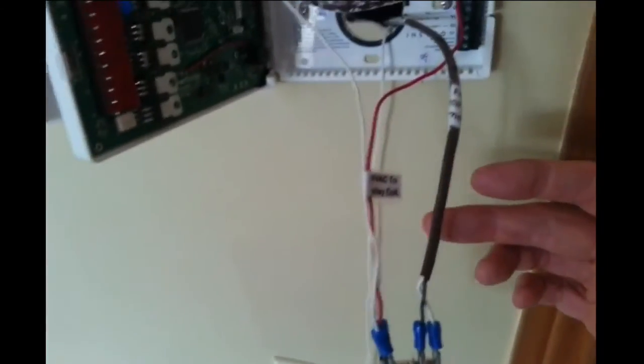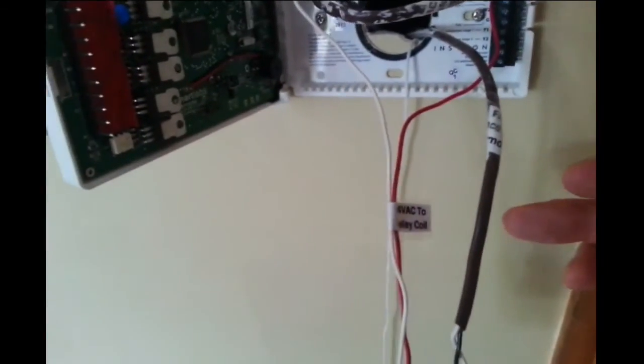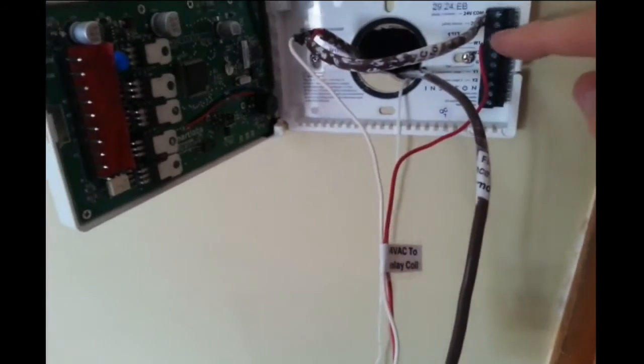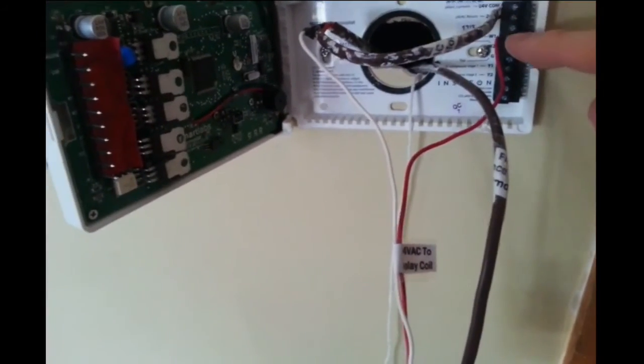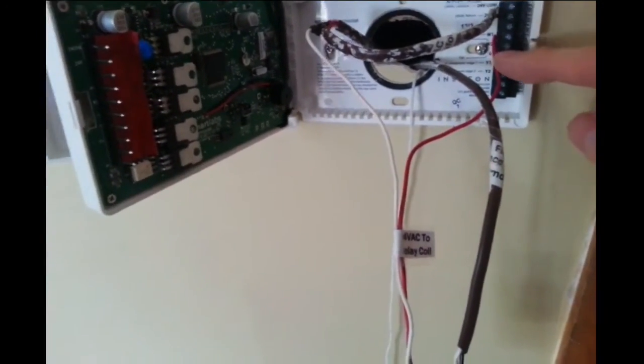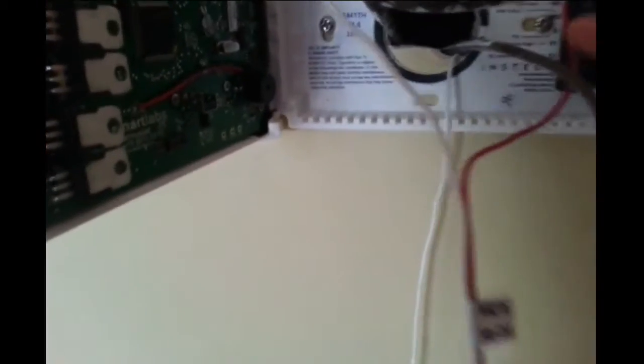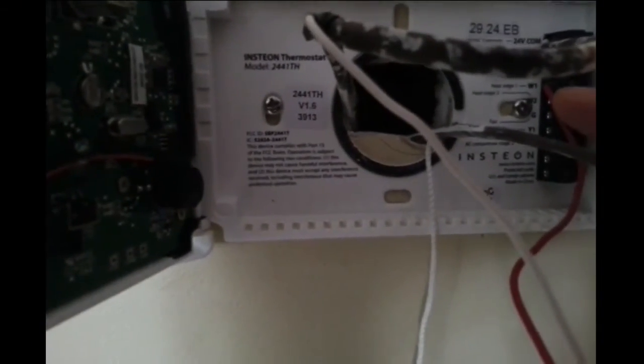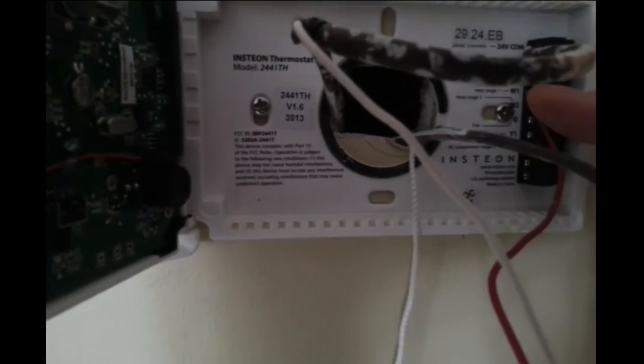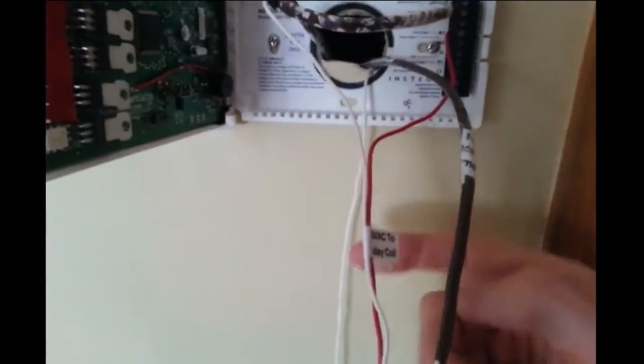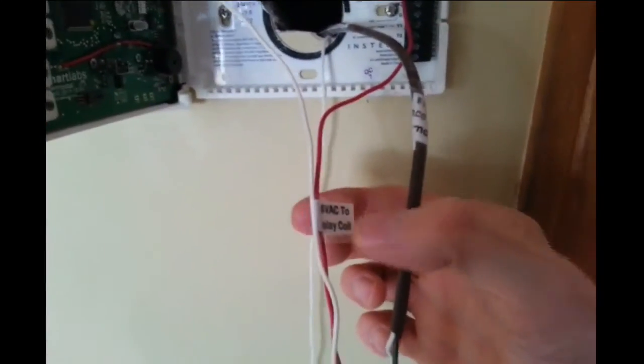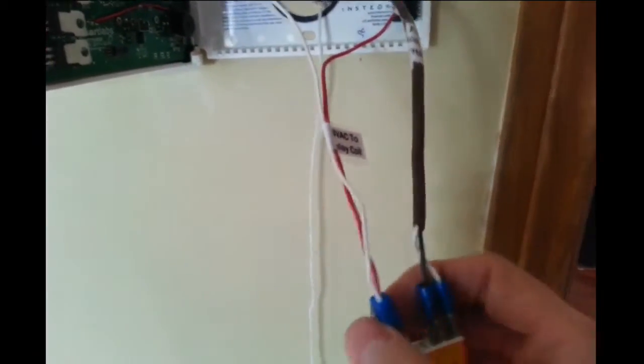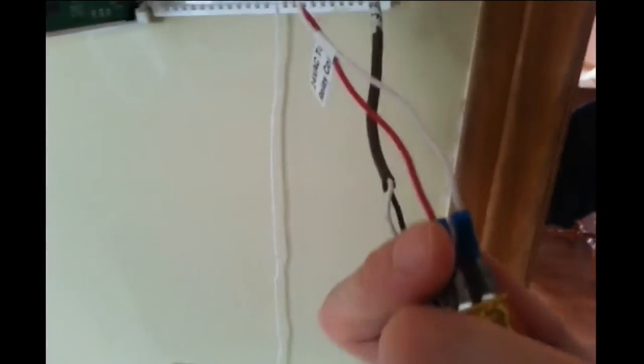So the other side of the 24-volt would come into the thermostat and then be fed out here whenever it needs heat. That's coming off of the W1 terminal on the thermostat, and then runs down to the other side of the coil.